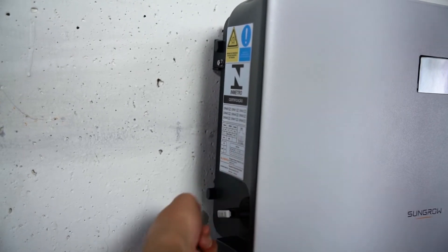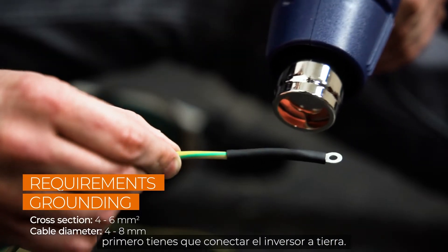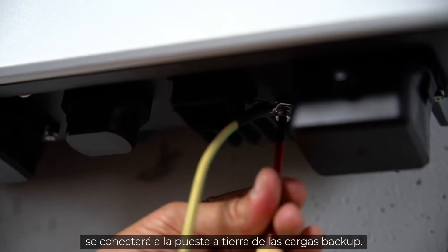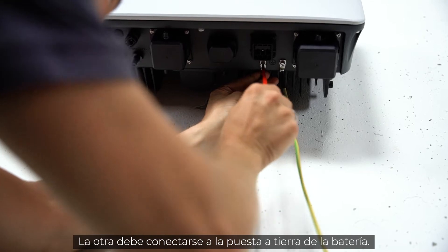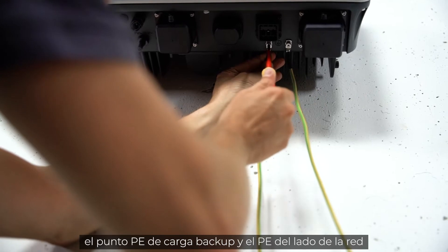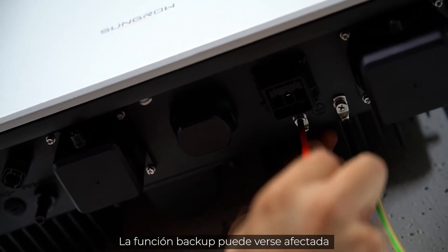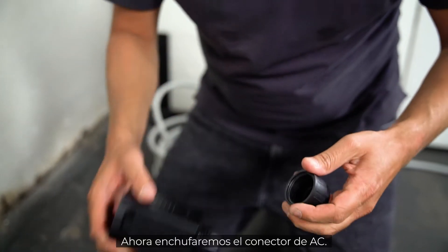Now let's continue with the installation. In the first step, connect the inverter to ground. There are two PE connections at the bottom of the inverter: the one below the backup port connects to the grounding of the backup loads, and the other connects to the grounding of the grid side. Make sure that the chassis of the inverter, the backup load PE, and the grid side PE are all connected to the same grounding point. If the grounding connection isn't done properly, it may affect the backup function.